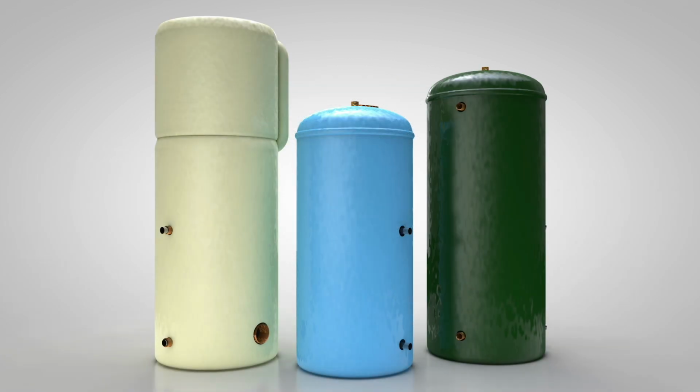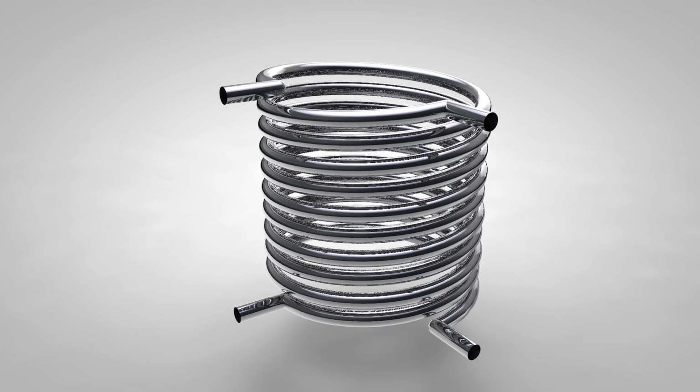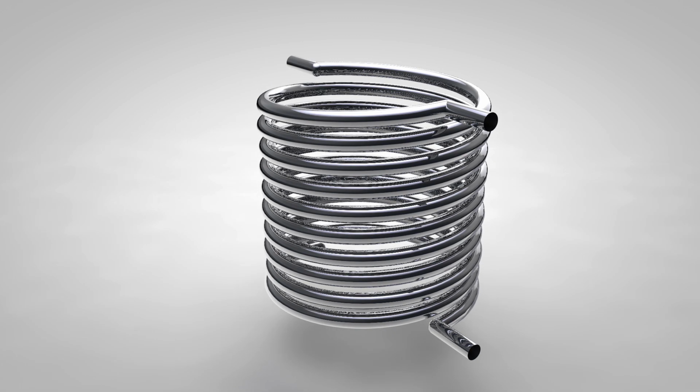Finally, let's look at the different options available for twin and triple coil cylinders and how multiple coils can be configured within a cylinder. In tall cylinders, coils can simply be stacked, one on top of the other. Stacked coils can have a dedicated volume of water attributed to them, for example in a solar system. The alternative is to interlace the coils so one fits alongside the other at 90 degrees or more commonly at 180 degrees. This saves space but means you can't dedicate volumes of water to a specific heat source.